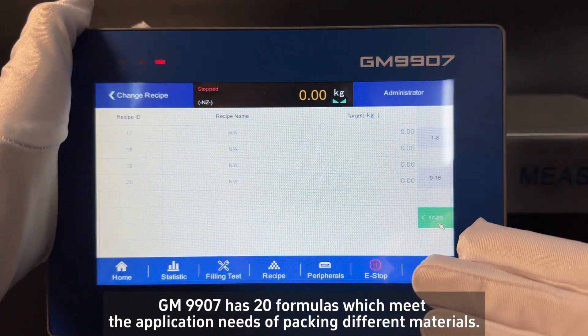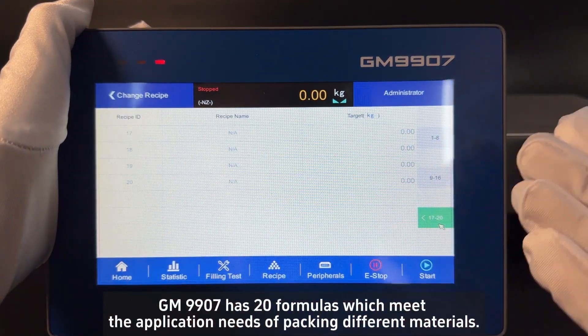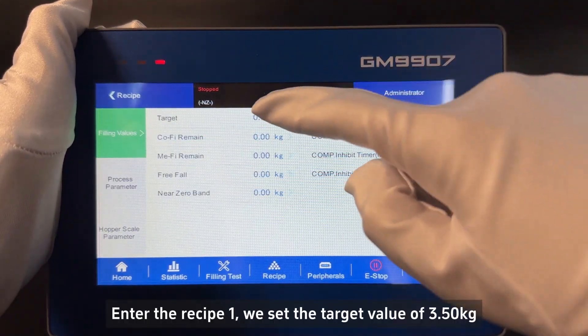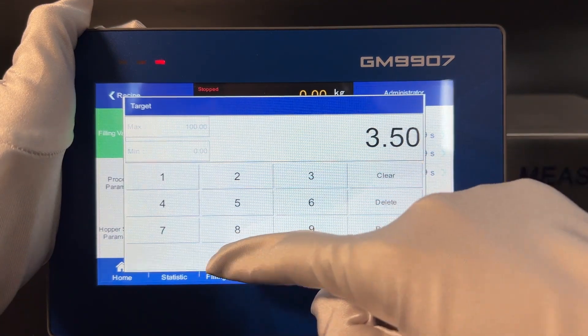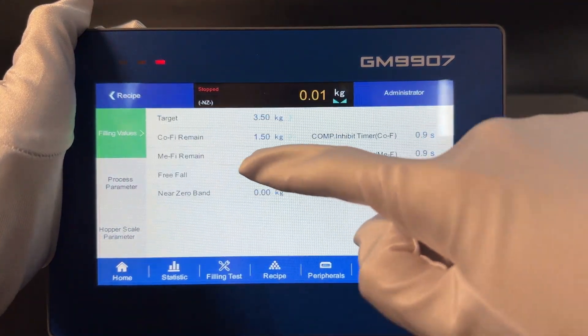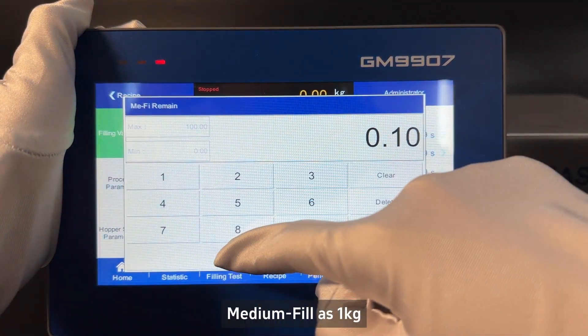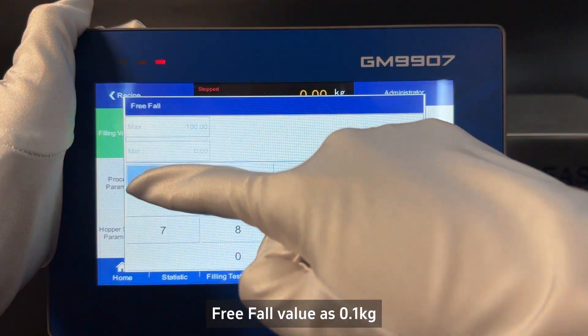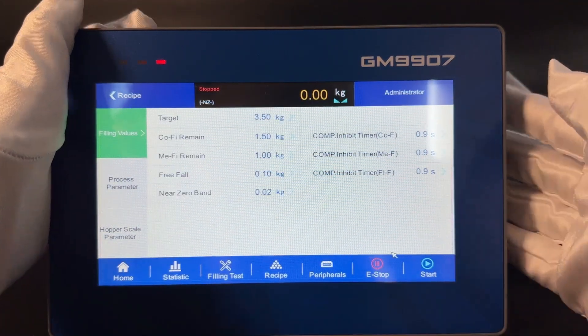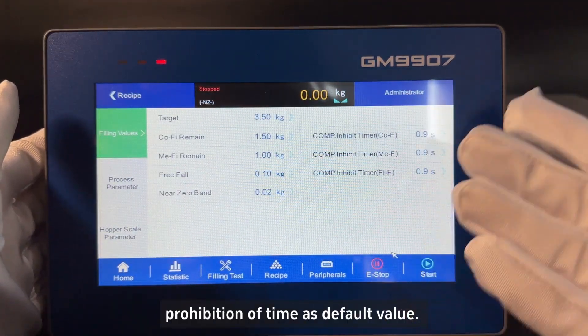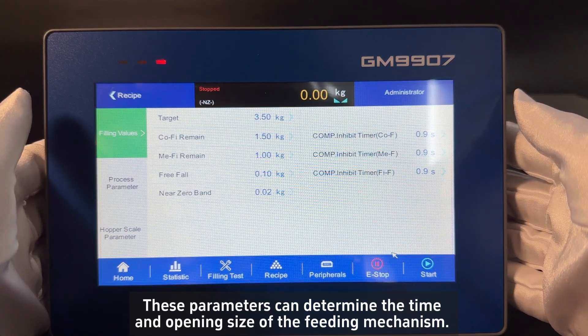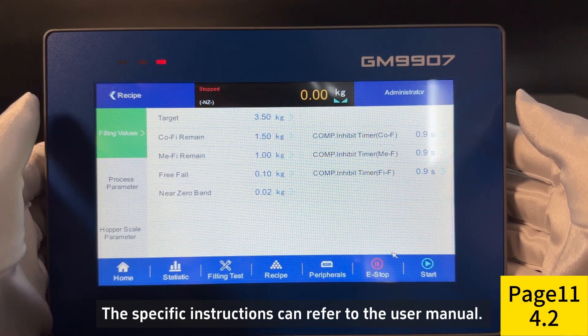GM9907 has 20 formulas which meet the application needs of packing different materials. Enter recipe one. We set the target value to 3.5 kg, fast fill as 1.5 kg, medium fill as 1 kg, free fall value as 0.1 kg, and near zero band as 0.02 kg. The prohibition time is left at default. These parameters determine the time and opening size of the feeding mechanism. Specific instructions can refer to the user manual.